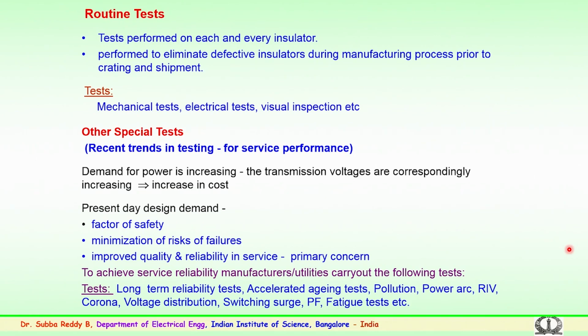The tests include long term reliability tests and the accelerated aging test. This particular test is carried out over a long period of time, from 1000 hours to 5000 hours, where acceleration factors like voltage and temperature are increased to a level depending upon the voltage and the string that is going to operate, and the tests are conducted for a long duration. Then there is the contamination or pollution test, which is again very important at extra high voltage and ultra high voltage. Power arc tests are particularly important for EHV and UHV voltage levels. Then the radio interference voltage and corona test: the discharges emitting from the hardware, the corona control rings or insulator accessories are very important, and these have to be examined.